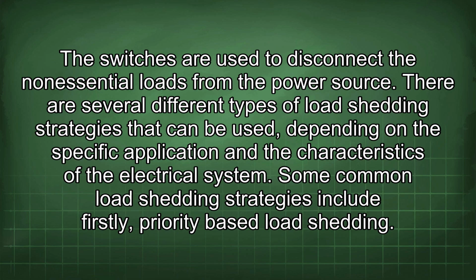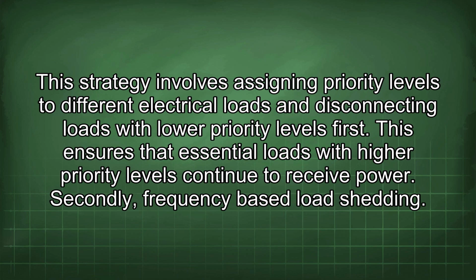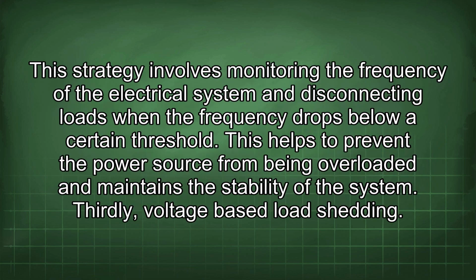Some common load shedding strategies include, firstly, priority-based load shedding. This strategy involves assigning priority levels to different electrical loads and disconnecting loads with lower priority levels first. This ensures that essential loads with higher priority levels continue to receive power. Secondly, frequency-based load shedding. This strategy involves monitoring the frequency of the electrical system and disconnecting loads when the frequency drops below a certain threshold. This helps to prevent the power source from being overloaded and maintains the stability of the system.